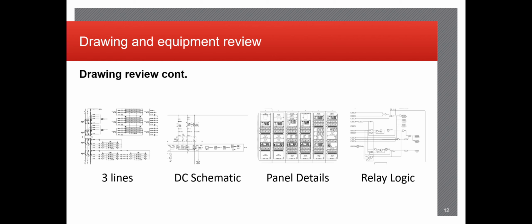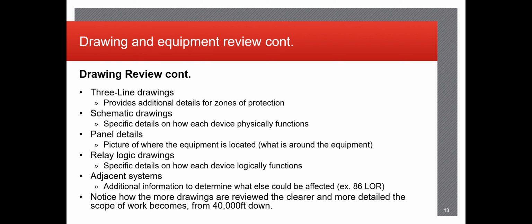And on the very far right is the relay logic diagrams. Those are always utilized for relay testing, understanding the functionality of some of the relay logic and how it should operate. Again, just going over all the necessary equipment, drawings, everything. Adjacent systems, additional information to determine what else could be affected. So again, the lockout relays, for example.